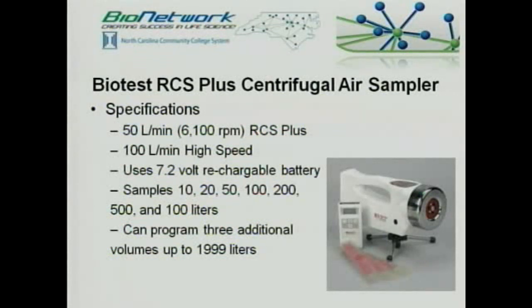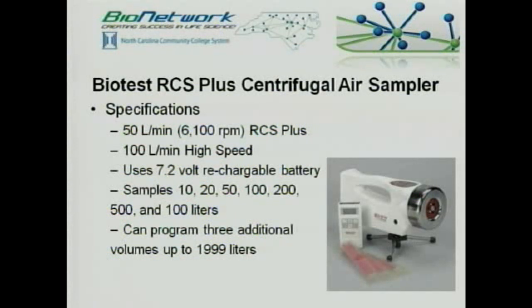The RCS Plus centrifugal air sampler I have samples 50 liters per minute, taking 20 minutes to collect 1,000 liters. The high-speed versions sample 100 liters per minute and take only 10 minutes. Each unit from Biotest Diagnostics comes with a 7.2-volt rechargeable battery and charger. It can sample volumes from 10, 20, 50, 100, 200, 500, up to 1,000 liters—the volume the FDA requires you to sample—and can be programmed for additional volumes up to 2,000 liters.